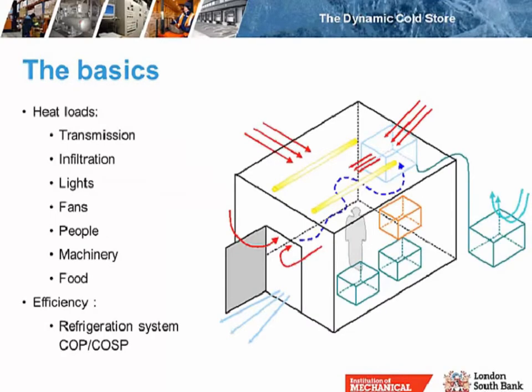I'd like to start with some of the basics, because I think some of this is quite important to understand. If you have a cold store like the diagram on the right, you're going to have a number of heat loads. These can come from transmission — the heat load across the insulation — from infiltration through doorways or gaps in the insulation, from lights, fans, people going into the store, machinery such as forklifts, and even the food itself if loaded above the store temperature. Things like transmission are related to location, orientation, and insulation thickness.